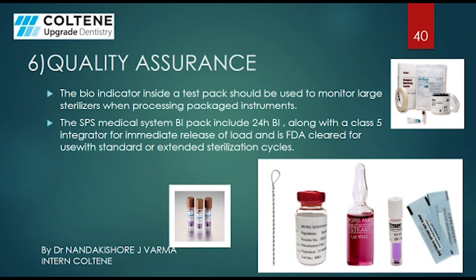The last step of instrument processing is quality assurance. A bioindicator inside a test pack should be used to monitor sterilizers when processing packaged instruments, so that we can assess the proper working conditions of the autoclaves or sterilization instruments. The SPS Medical System BI pack includes 24 biological indicators along with a class 5 integrator for immediate release of the load and is FDA cleared for use with standard or extended sterilization cycles. It's an example of a bioindicator.